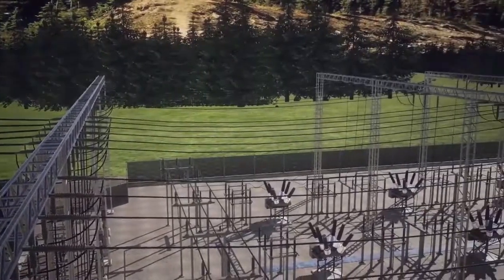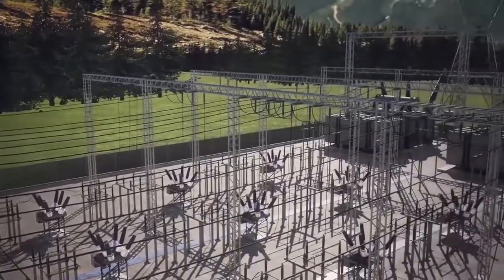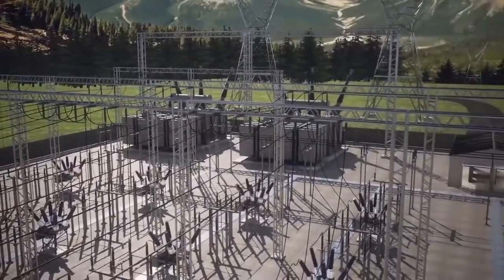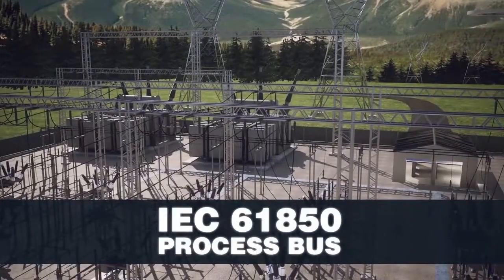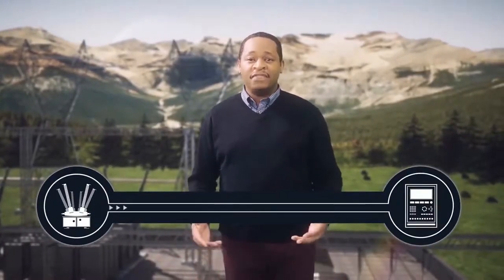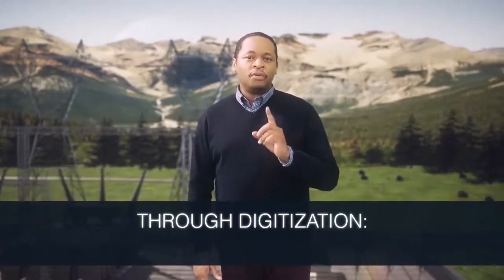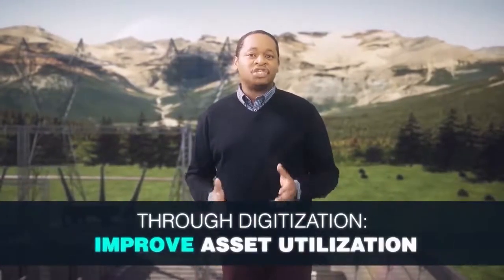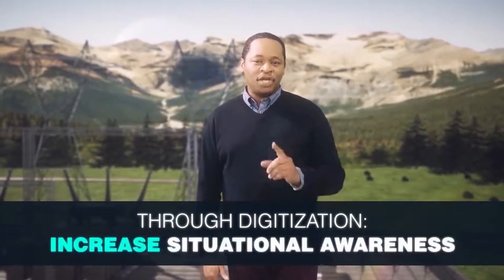Using virtual reality, I'm going to take you on a journey to see the transformation of a substation and the amazing business opportunities that digitizing a substation can provide. We're looking at a conventional 400 kV air-insulated substation. Today, we're going to digitize our primary equipment, introducing an IEC 61850 process bus. A process bus enables the movement of data from a primary asset, like a circuit breaker, to protection relays and automation devices in the control room. Through digitization, you will see how to reduce resource requirements and achieve greater asset utilization and situational awareness.